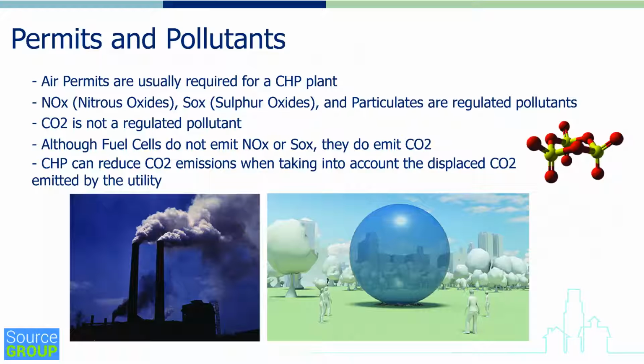NOx, nitrous oxide, and SOx, sulfur dioxides, and particulates are regulated pollutants. Those are used in the permitting process, and the levels of those made are generally incorporated into the permit conditions. Again, the permit itself can be complex. If the cogen operator is required to have a Title V permit, there are various reporting requirements. It has to be recorded every time the plant started up and shut down. The annual fuel usage has to be accurately reported every year, things like that.